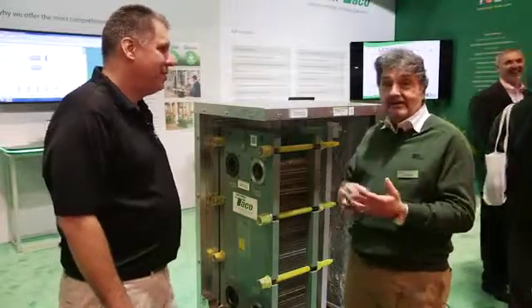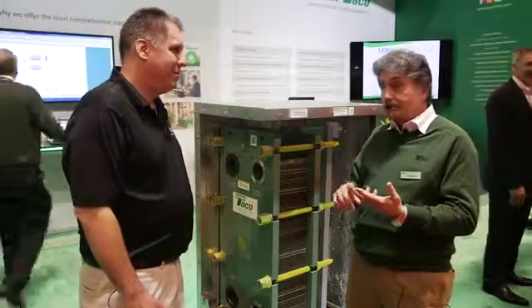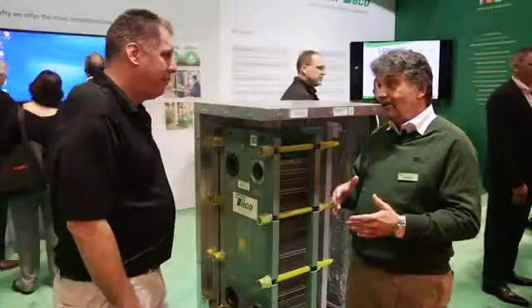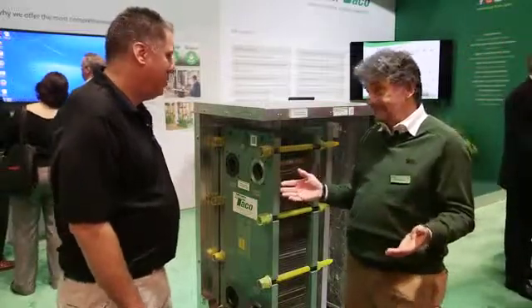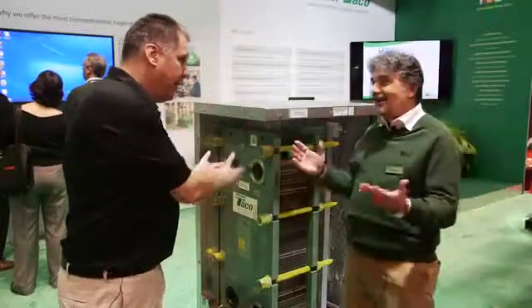One is temperatures, the inlets, the outlets. We would need pressure drops, and then we would need your flow rates, and then we can calculate that. Or you can give me a heat load and your inlet temperatures and outlets, and I can calculate your flows. So once you engineer it, you just figure how many plates you need, bolt them together. Thank God for computers, right?